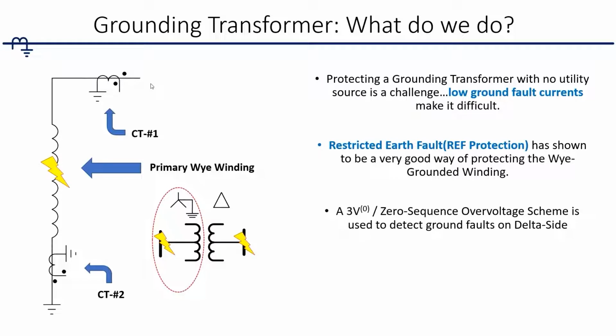So a lot of companies have gone with something called REF, which is restricted earth fault protection, which is really, really good. As far as simulations go and real world experience, I have seen where this has been really, really good. I've seen several instances where it tripped when it was supposed to, and there was actually an internal fault in the transformer. It worked perfectly in a microgrid setting, so that was pretty good. I've seen this work pretty reliably, so that was always good to see.